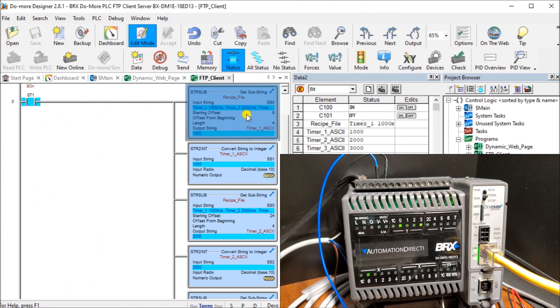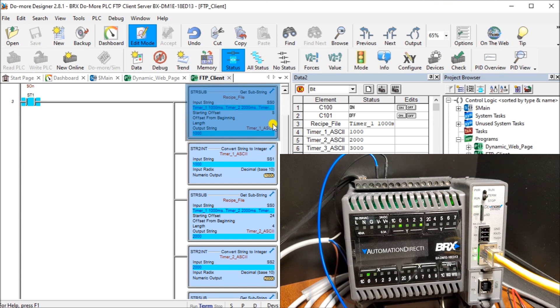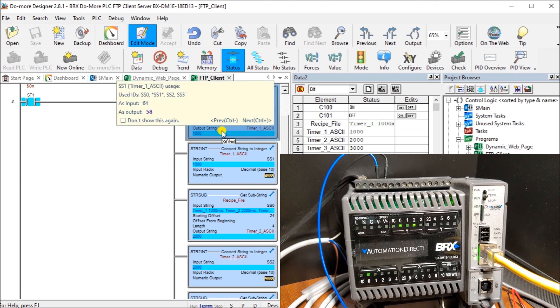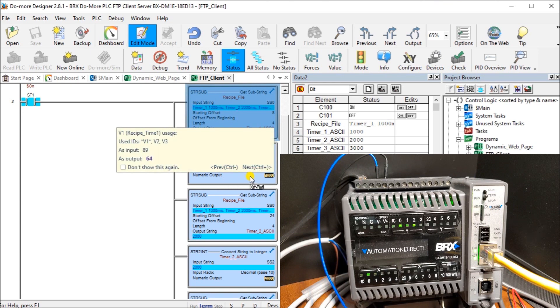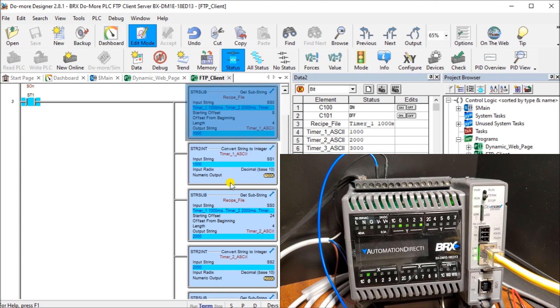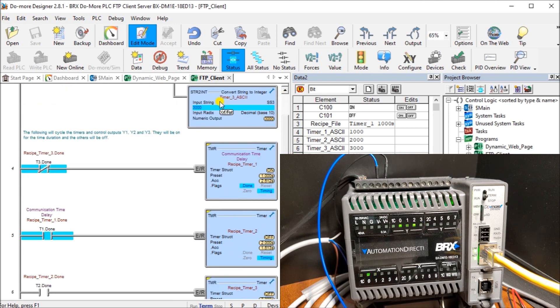Once we have our string in SS0, we want to take that input string and break it up. We take the eighth byte or character over, and we read four of them. Then we put it in SS1 and SS1 gets converted using string to integer to V1 memory location. Once we have it on V1, then we can use this later on in our program. We do the same thing with timer number two and timer number three.